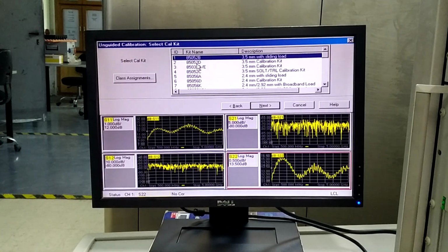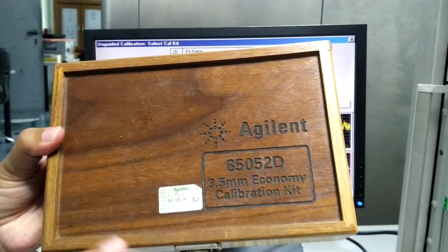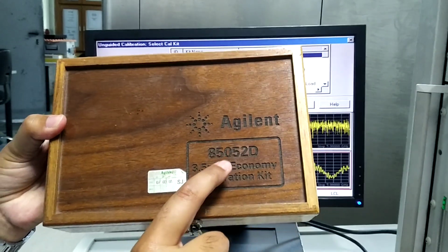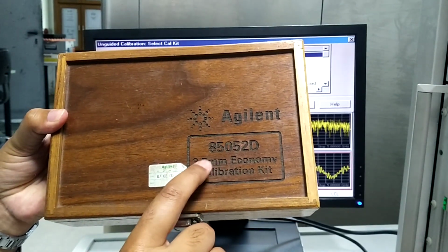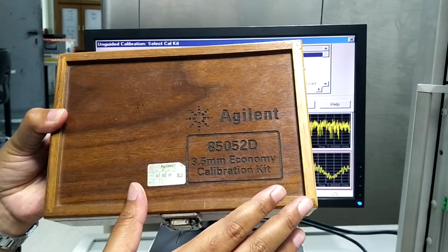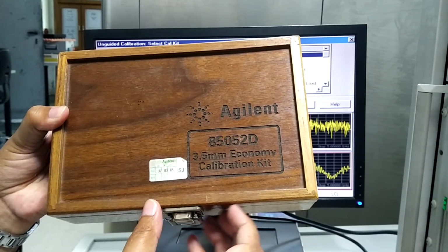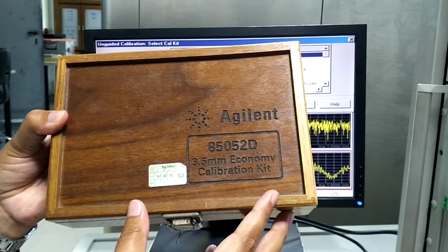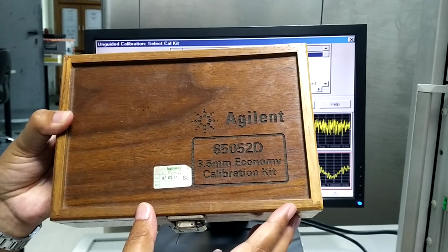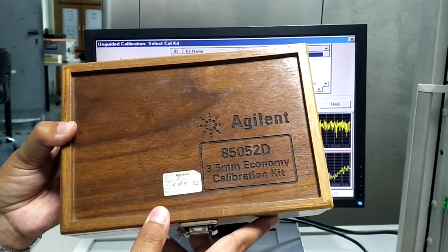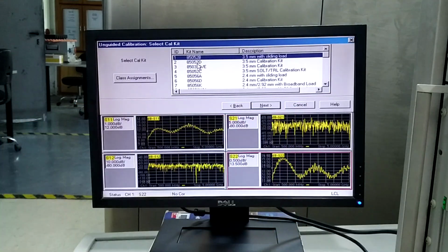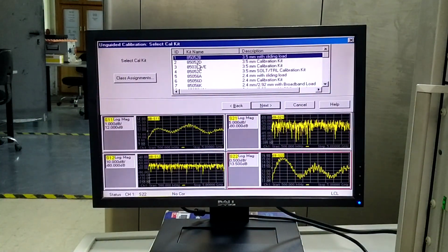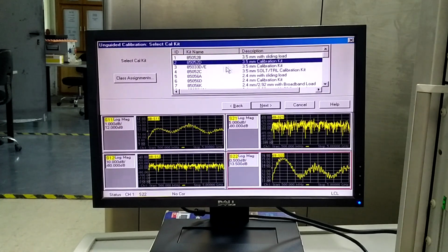Let me show you the calibration kit box. This is a calibration kit box made by Agilent Technologies. This is the 85052D, a 3.5 mm economy calibration kit. Economy means it has a smaller number of components inside, but it has all the essential calibration standards that can be used to perform the full two-port calibration. So this is the kit that we will use, and since we know the number on top of the kit is 85052D, I select this option, 85052D. It is a 3.5 mm calibration kit. I select this one and click the next button.